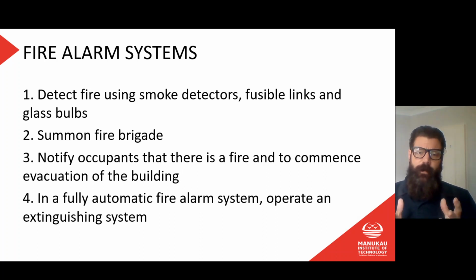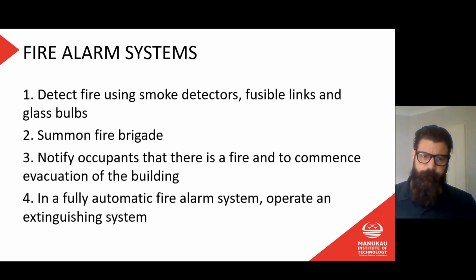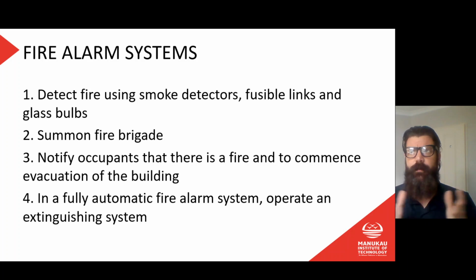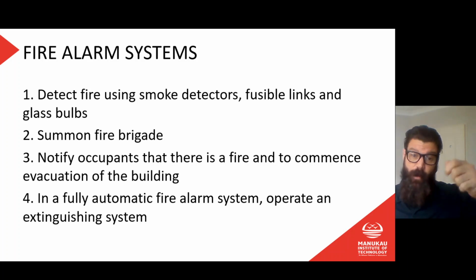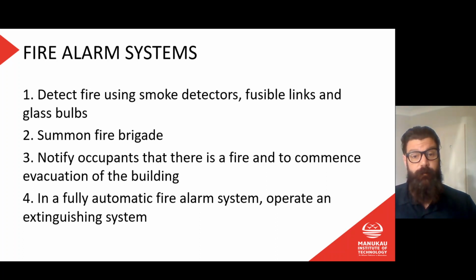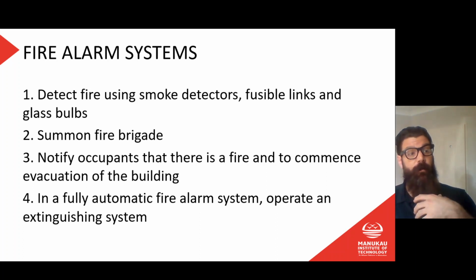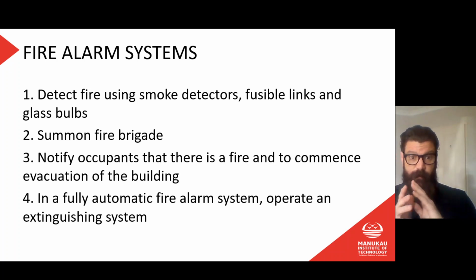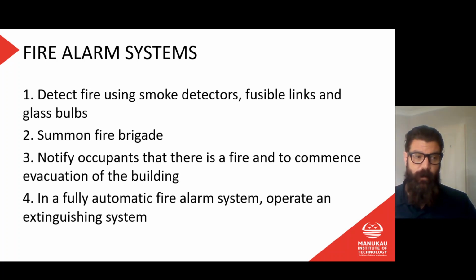They will always notify the occupants, so that's your alarm going off, whoop, whoop, whoop, or ring, ring, ring, whatever it is. And they may also operate the extinguishing system, or they could be connected to other things. An example would be buildings where you have swipe card access in and out. Often those swipe card systems will be connected to the fire alarm. So if the fire alarm goes off, the fire alarm control panel sends a signal to the controller for the swipe doors saying it's a fire, unlock every door, and then all the doors unlock, so people don't have to swipe their cards to get out of the building.